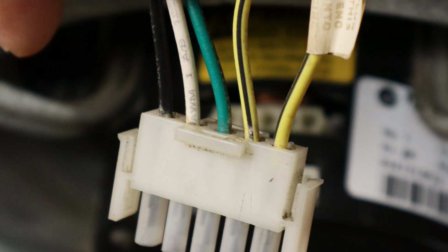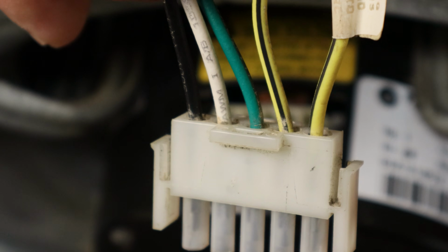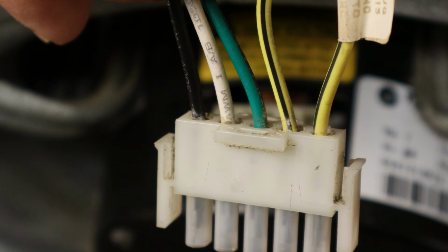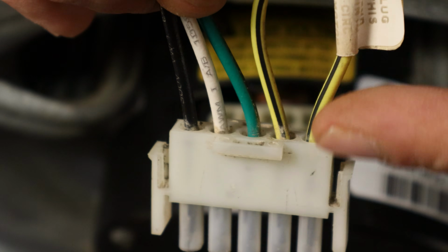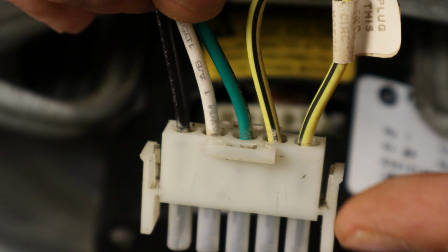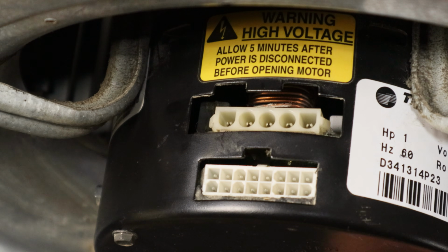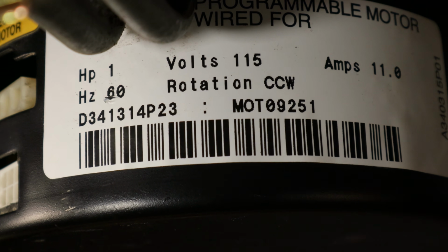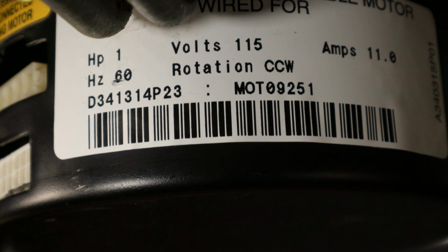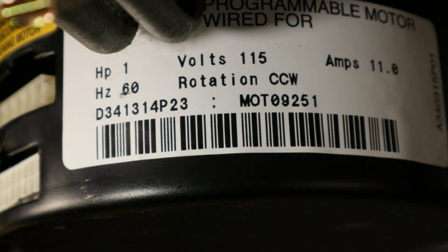We're going to put this Molex plug in here. The black wires are 120 coming in. The white is our neutral. Green is our ground. You see this yellow wire here. It's a jumper. Some motors can be converted from 115 to 230. So they can go in a furnace or an air handler. And you can see here the sticker right on the side of the motor. It's only rated for 115. So that jumper doesn't do anything.